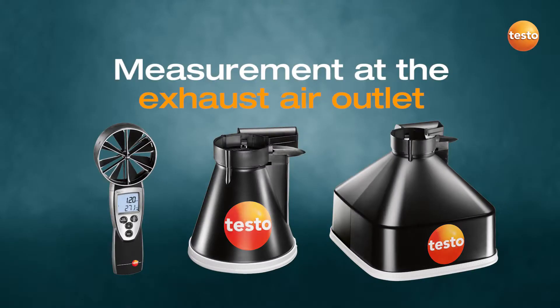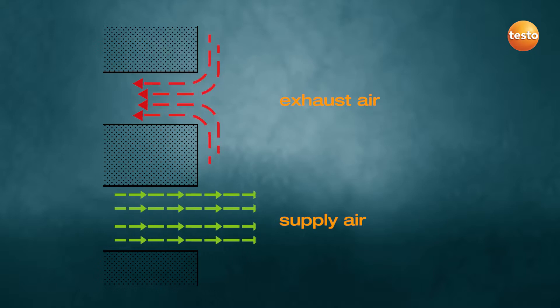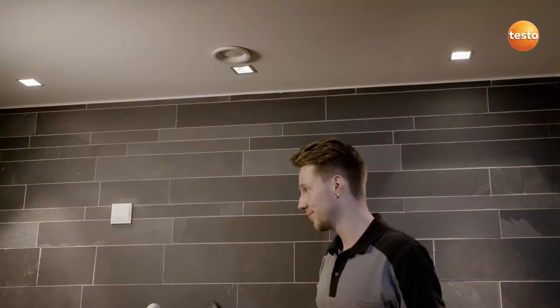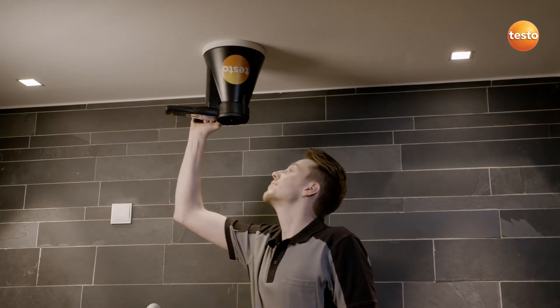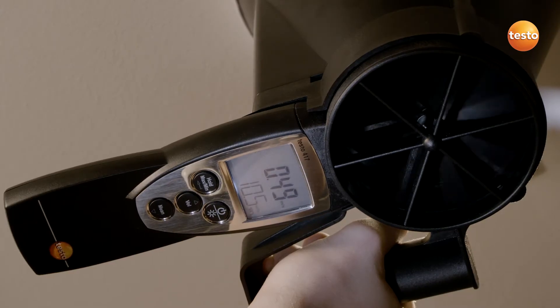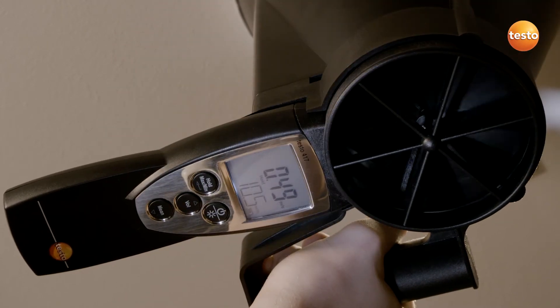This is how you measure properly at the exhaust air outlet. A funnel is required to measure the exhaust air. There is no directed flow profile available for exhaust air, as the air is sucked in funnel-like from the room. This means there is no definable area in the room via which the volume flow can be determined. This challenge is easily solved with the Testo 417 funnel, because it creates defined flow conditions at some distance from the plate outlet in a fixed cross section.